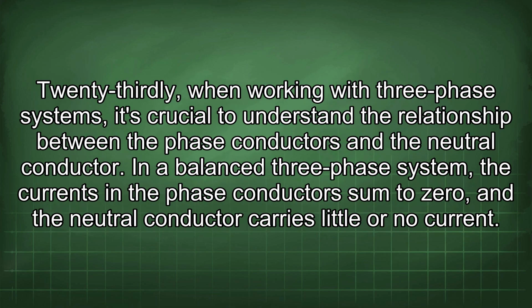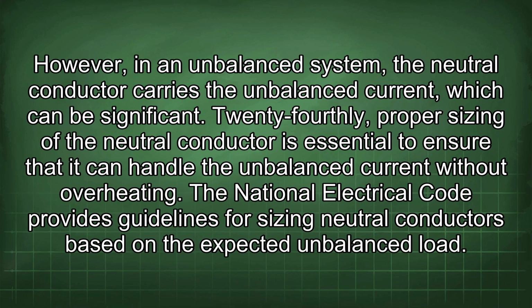23rdly, when working with three-phase systems, it's crucial to understand the relationship between the phase conductors and the neutral conductor. In a balanced three-phase system, the currents in the phase conductors sum to zero, and the neutral conductor carries little or no current. However, in an unbalanced system, the neutral conductor carries the unbalanced current, which can be significant.